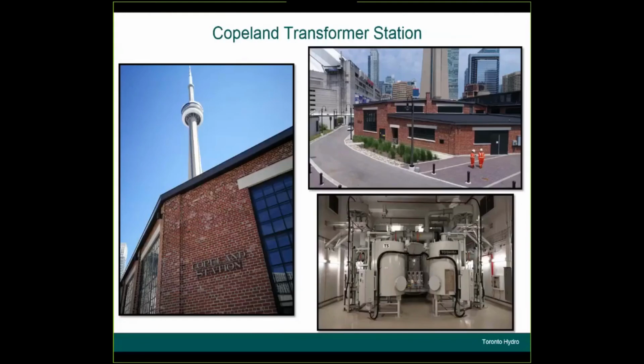And that is the conclusion, though I'd like to show a quick video of our transformer delivery. But this is what the finished product looks like with the gas-insulated transformers in place. We have 2 transformers that were installed for phase 1. We are now in the process of executing phase 2, where there will be 3 more transformers added, 2 attached to medium voltage distribution switchgear, and 1 a spare transformer in the event that we have any issues with any of the other 4. There's a full sparing concept that will be executed to enable transformer 5 to pick up any one of T1 to T4 buses.